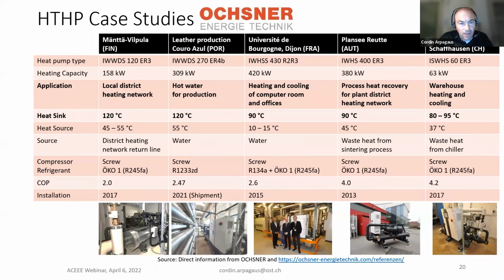The heatsink temperatures here are higher than 80, 90, 120 degrees - these are installed case studies in the field. The heat sources are around 45-55 degrees. You can also see the compressor type, which is all screw here, the key technology of these heat pumps from Ochsner. The COPs achieved depend on temperature conditions, but you can see it goes up to 4.0, 4.2 if the temperature lift is not too high.